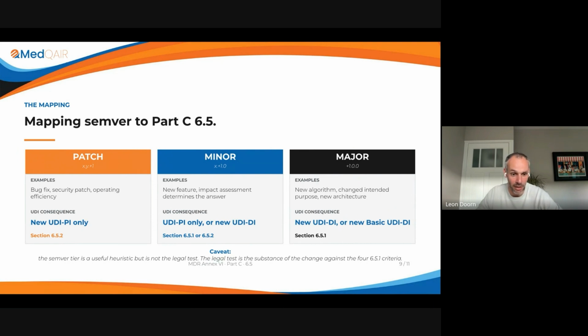we don't do a new UDI-DI, only a new UDI-PI, because only the UDI-DI goes into EUDAMED. However, if you want to avoid having to do a lot of registrations in EUDAMED, you can create a separate layer where in your minor change procedures you evaluate, hey, is this one of the changes according to the MDR that should be seen as a change that impacts the registration? And then potentially only a part of your minor changes need to be given a new UDI-DI.